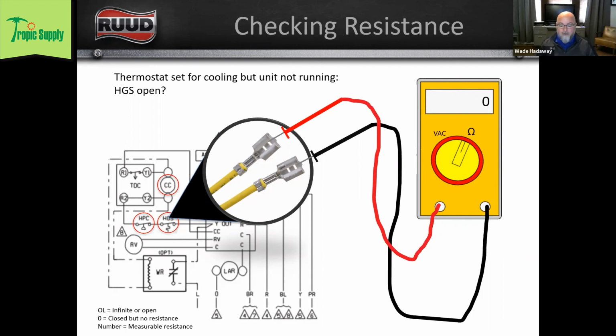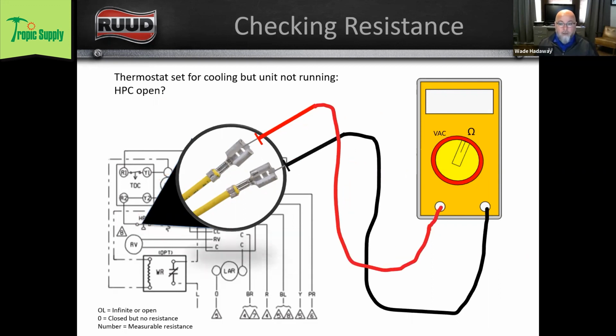And we can see that we have 0 resistance. So our switch is closed, right? If it was open, it'd read OL. We have no measurable resistance, so that switch is good. We're going to do the same thing with the high pressure control. And on the high pressure control, it reads OL because it was open, right? Now, none of this is telling us that we have a bad pressure control. It's just telling us that pressure control is open. Why is our high pressure control open? That's another topic for another day.